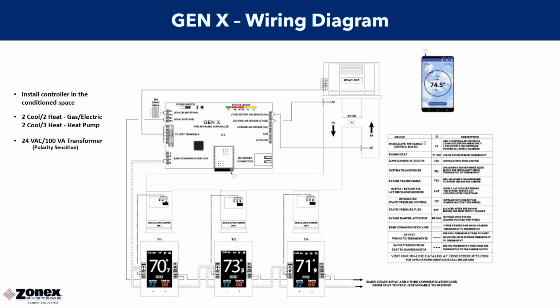On the TR1, TR2 out terminal, we're going to carry that 24 volts in a daisy chain fashion using 18 gauge thermostat wire, which will daisy chain to the first zone thermostat TR1, TR2 terminal on its subbase and continue that daisy chain all the way through until we dead end at our last thermostat. Along with daisy chaining the 24 volts, we are also going to daisy chain our RS-485 communication cable. This is a Zonex spec cable and should be supplied to you with your order. This will wire in off the A and B terminal in the bottom left-hand corner of your Zonex controller and will wire to the A and B terminal on the subbase for your first zone thermostat, and you will continue daisy chaining in and out of that A and B terminal until you dead end at your last thermostat.